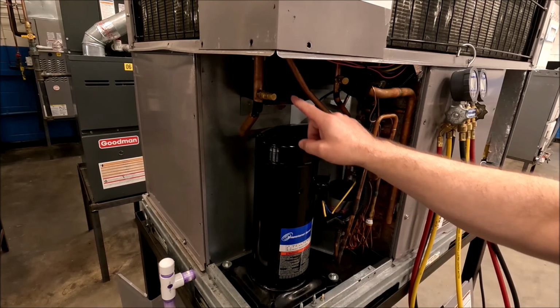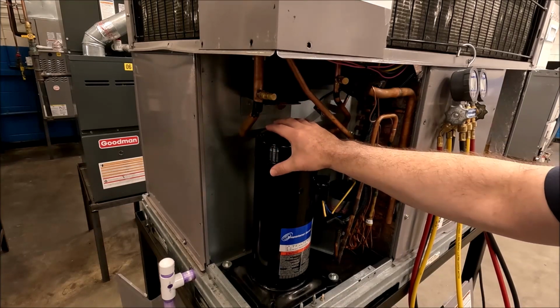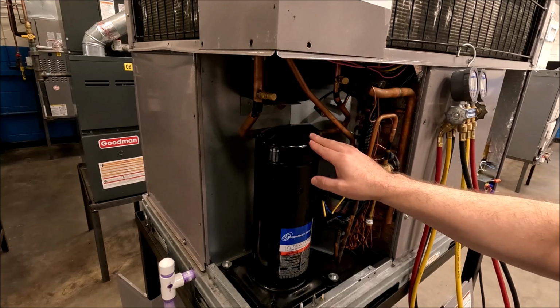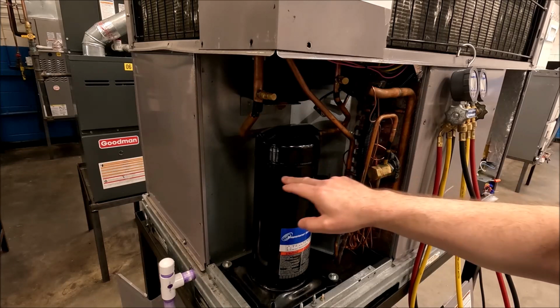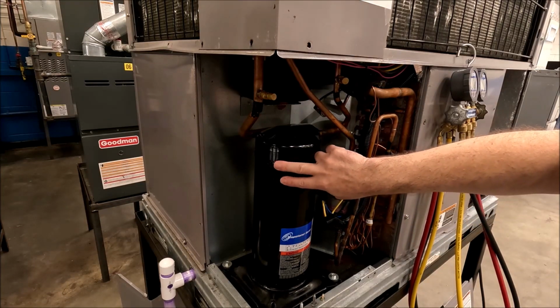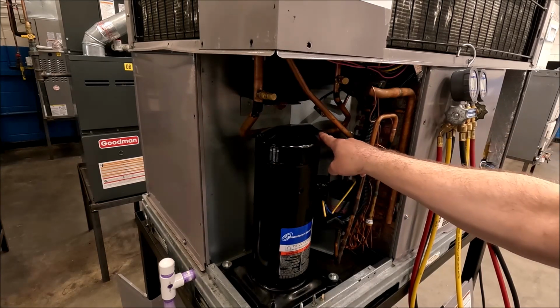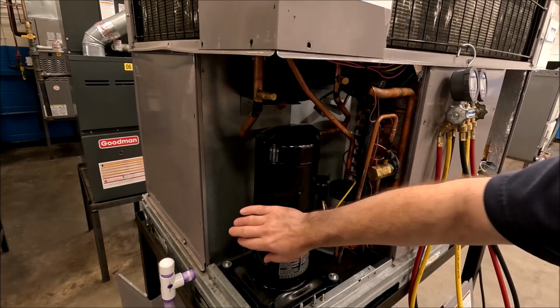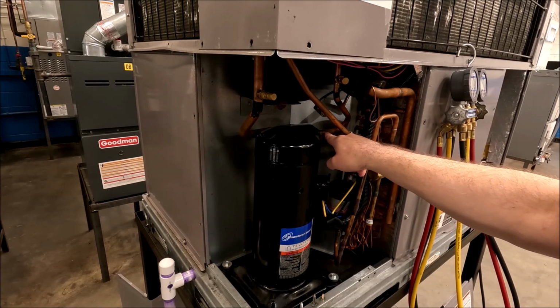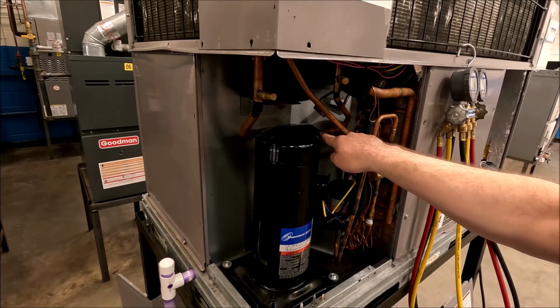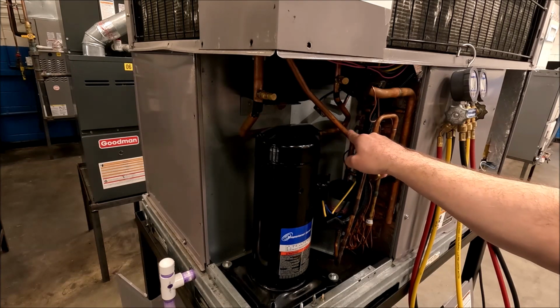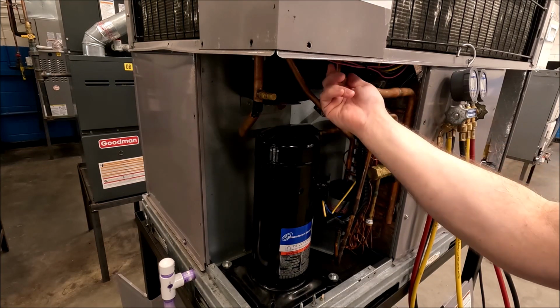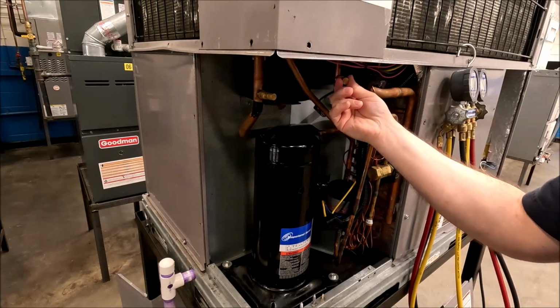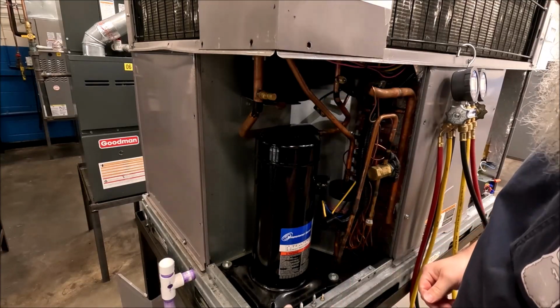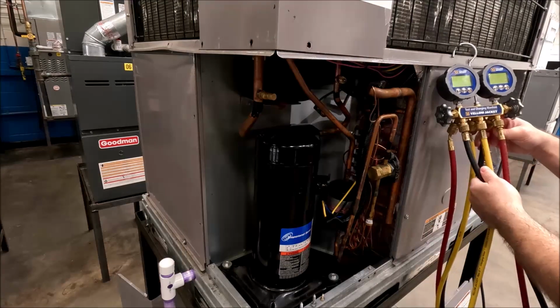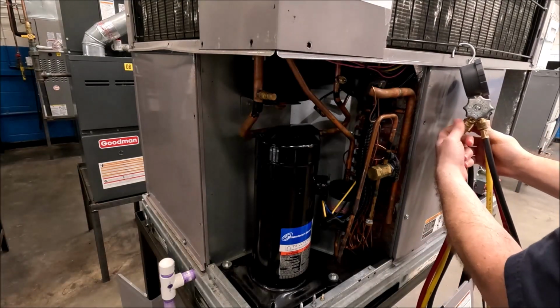So what I'm going to do here is, if you look right here on this left-hand side, this scroll compressor, the discharge line on the scroll compressor is at the top. So as we look right here, and you have to know what type of compressor you got, this weld line right here, you got your scrolls orbiting and stuff right here, compressing the refrigerant vapor, and this line over here is our discharge line. It's warm where the rest of the compressor is cool. That line is going to be the hottest temperature point, and that line is going to be very warm. And if you look and you follow it, a little serpentine effect, there's an access point there. That's going to give us our pressure for the high side of the system. So I'm going to take that cap off, make sure it's got a little O-ring in it, and I'm going to put my high side pressure gauge, I'm going to hook it up there.